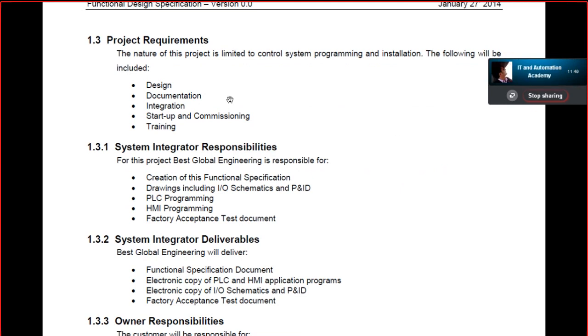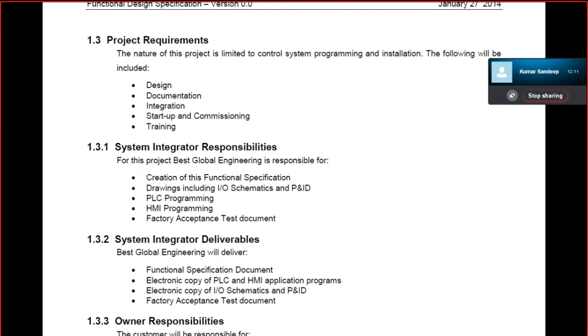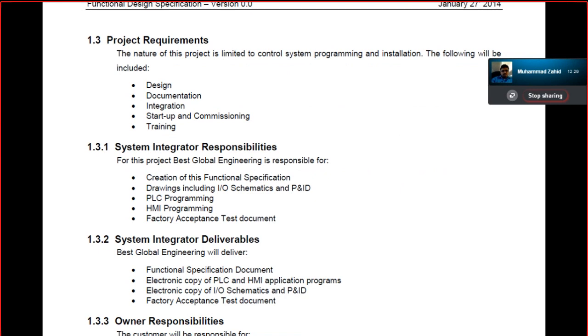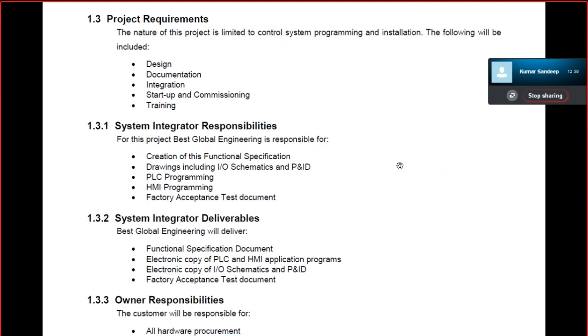The system integrator will create the functional requirements document — this is the first document you are going to deliver, which I am showing on screen right now. The second deliverable is drawings. P&ID drawings are not normally the responsibility of a system integrator, but for a small industrial project like this you may need to draw the P&ID yourself by summarizing the process the operator describes. Then comes PLC programming, factory acceptance test documents, and so on.